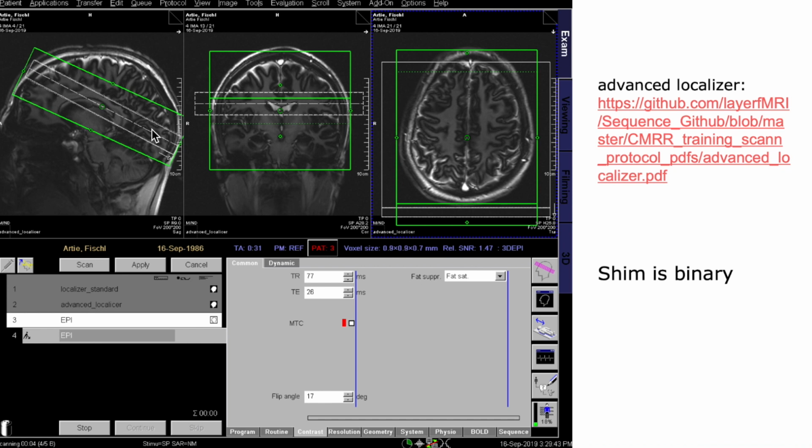And this means that for a small shim box, as small as the imaging volume, you would only have 2-3 voxels of your field distribution within your field of view. And it's obviously impossible to fit higher order spherical harmonics of your shimming to these 3 voxels, right? That's why it's more beneficial to use larger shim boxes, as indicated here in green.